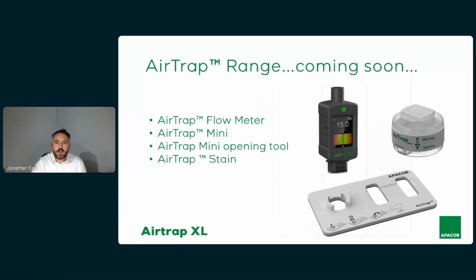This is a flow meter for calibration of your pump and cassette. But what's unique and different about this flow meter is it's a digital electronic flow meter. It's very accurate and very sensitive. It displays the airflow in litres per minute to 1 decimal place. So it displays the flow rate during your calibration in both a numeric form, but also has a simple to use heat map style scale beneath that. And this is for just very quick and easy calibration.